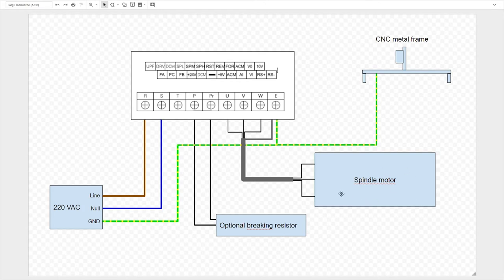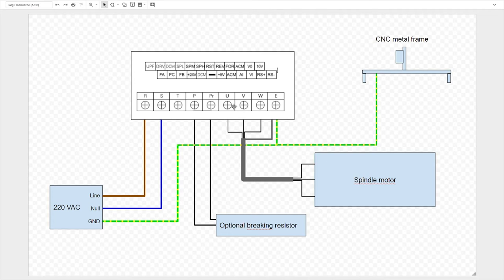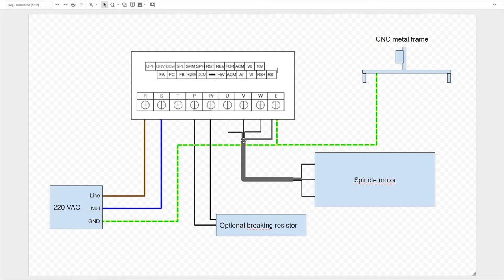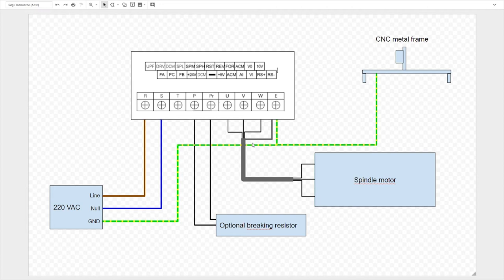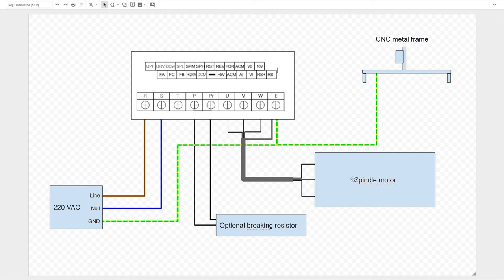So how do you connect the spindle motor? Well, it's very simple actually. You just connect U, V and W via three wires to the spindle motor and they can be connected in any combination you want. If the spindle motor then rotates in the incorrect direction, you can just swap any one of these two and it's gonna go in the opposite direction. And then this gray part is supposed to represent a shielded cable. So a shielded cable is basically like three or four wires that are wrapped in some kind of a metal shell and you take that metal shell and then you ground it. That means that any of the interference that these three wires are gonna induce will go to earth. So you need ground to be safe and also to reduce all the electrical noise that the spindle motor creates.